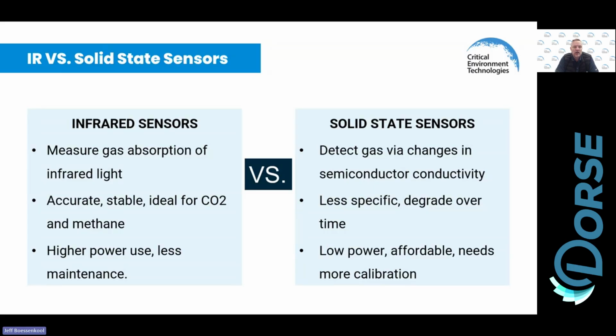And that's why we have made the strong recommendation, when we are monitoring refrigerants, that we utilize an infrared sensor. So instead of the sensor having an electrolyte inside, it's got a series of mirrors and light refractions where it is able to very specifically look for that specific target of refrigerant, whether it be R454B, R410A. And it's not as susceptible to cross-contamination or poisoning. It's going to last about 2 to 3 times as long. You can get up to 15 years with an infrared sensor. In addition to that, your calibration is only required every couple of years, okay? It doesn't have the same issues with drifting like a standard solid-state sensor would, right? So again, for refrigerants, we would make a very strong recommendation that we utilize an infrared sensor.